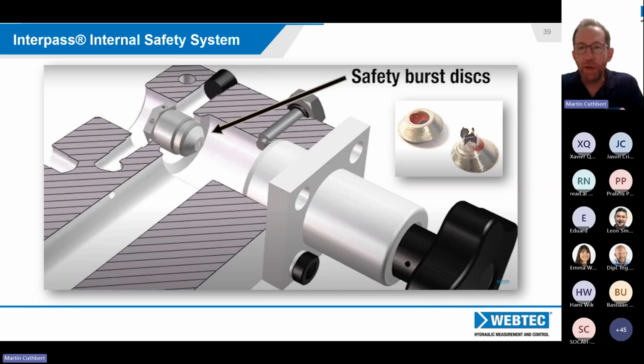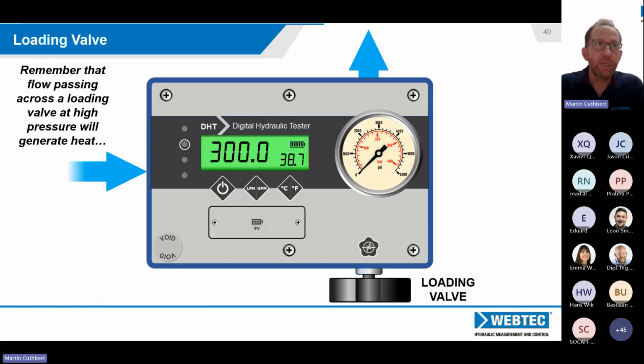So if we think about the loading valve, which incorporates this Interpass system, let's look at this example. The flow's coming in from the left. Bear in mind a loading valve is a restriction, and wherever you create a restriction, here we're loading the system, restricting the flow through the tester, we can see the pressure's going up. We can see the efficiency of the pump goes down as the pressure increases. We can see the flow has dropped off a bit, but wherever you're creating a pressure drop, you're also generating heat.